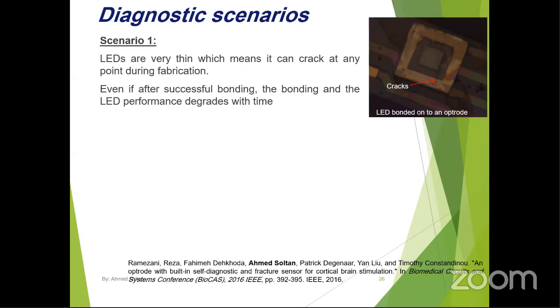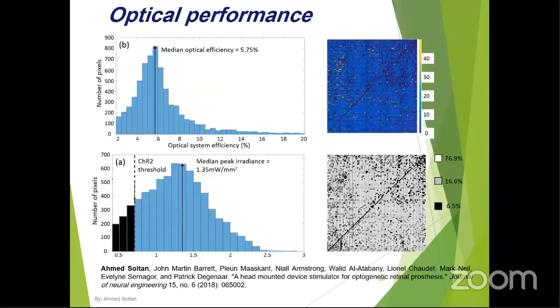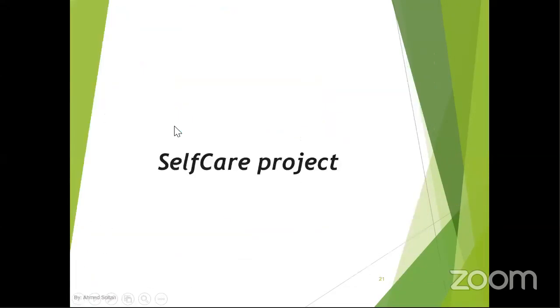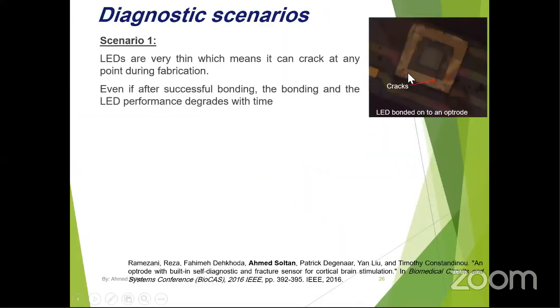Okay, so one of the most common scenarios is the LED. For the stimulation, the bond pads of the LED, the places where you stick the LED, are sometimes not very efficient. If we go back to this slide, you can find a very big variance in the LED stimulation level between different pixels. The main reason for this variance in the stimulation level is the bonding efficiency. The bonding efficiency means how you fix the LED on the Optrode or on the LED matrix, or how the electrodes behave over time. It changes over time, so it's very important to monitor. One of the very important things is the LED bonding, whether you can detect if the LED is cracked or not.